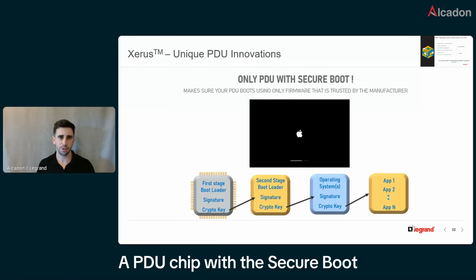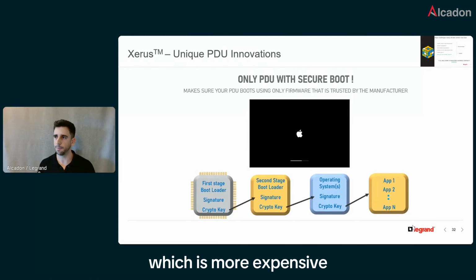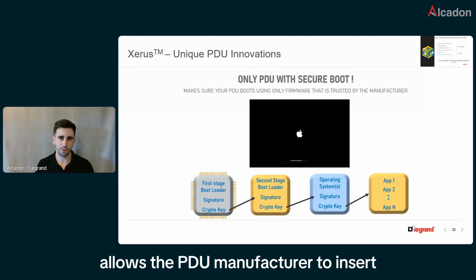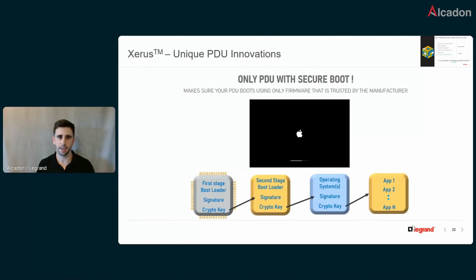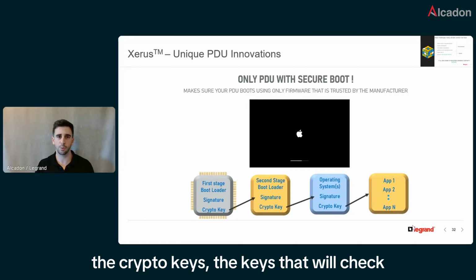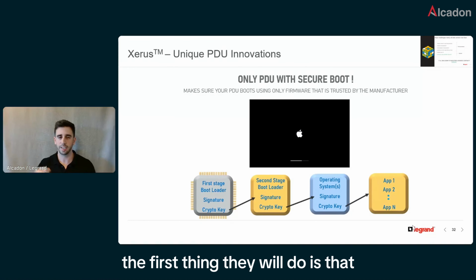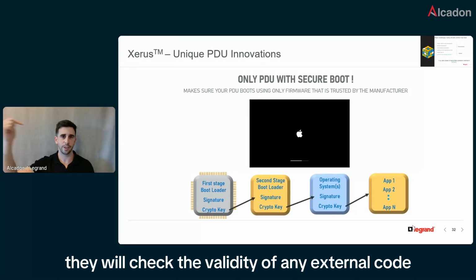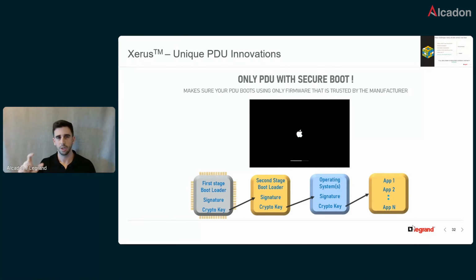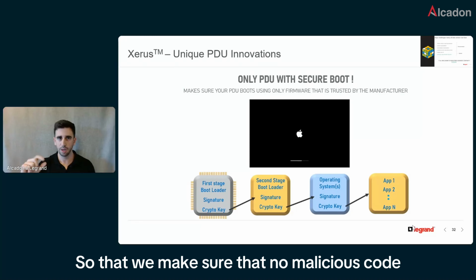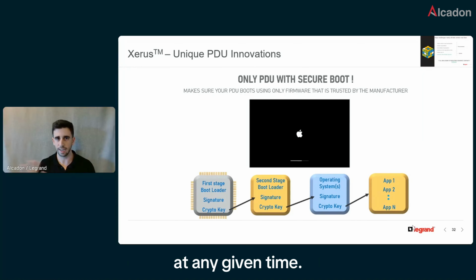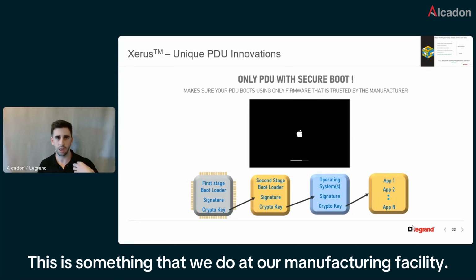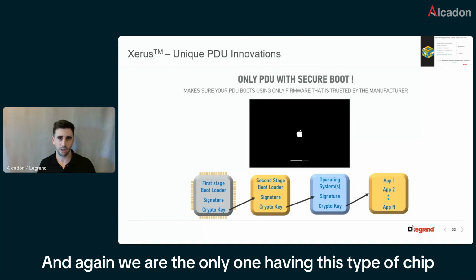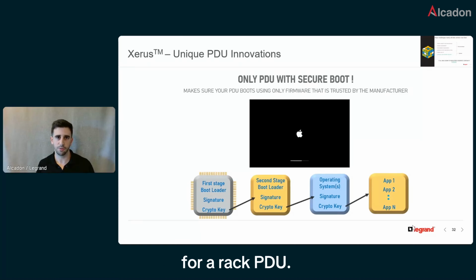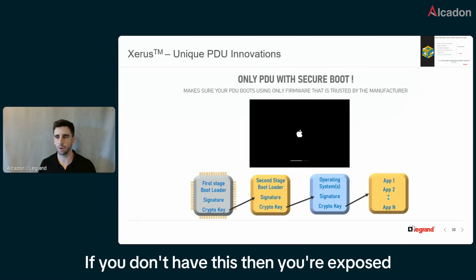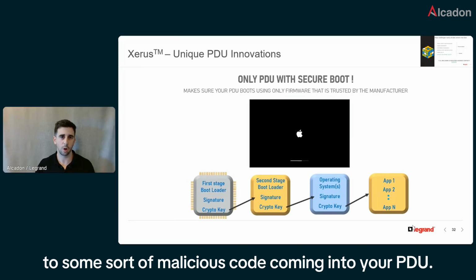A PDU chip with Secure Boot, which is more expensive, allows the PDU manufacturer to insert the crypto keys that will check the validity of any external code coming into the PDU, so that we make sure no malicious code is being installed into your PDU at any given time. This is something we do at our manufacturing facility, and again, we are the only one having this type of chip for a rack PDU. If you don't have this, then you're exposed to some sort of malicious code coming into your PDU.